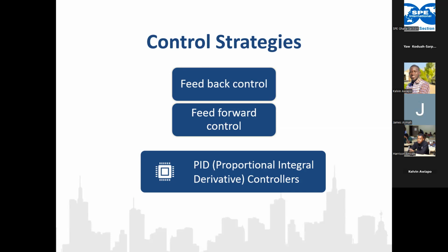Usually it is done at the engineering phase, to see which one will be needed, or if there's a modification in the plant, you have to tune it again to see which ones will be needed at a point in time, and the percentages or how much you will need for each of them. It's actually mathematical calculations, and in the system you key in the various values to tune it.